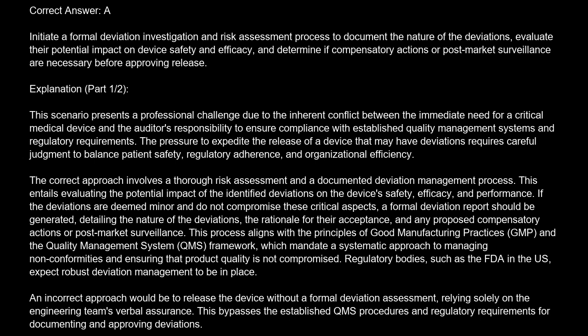This entails evaluating the potential impact of the identified deviations on the device's safety, efficacy, and performance. If the deviations are deemed minor and do not compromise these critical aspects, a formal deviation report should be generated, detailing the nature of the deviations, the rationale for their acceptance, and any proposed compensatory actions or post-market surveillance. This process aligns with the principles of good manufacturing practices, GMP, and the Quality Management System, QMS, framework, which mandate a systematic approach to managing nonconformities and ensuring that product quality is not compromised. Regulatory bodies, such as the FDA in the U.S., expect robust deviation management to be in place.